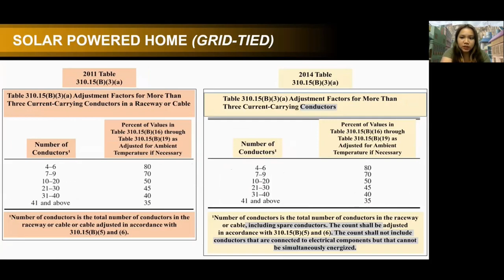Tapos ito pa din. So ito yung steps in PV system conductor sizing. First is look for the ISC rating of the PV cell. Second is multiply by 2 safety factors, which are irradiance and continuous duty. Third is refer to table 310.15 B16 for the size of wire. Yun yung pinakita natin kanina.